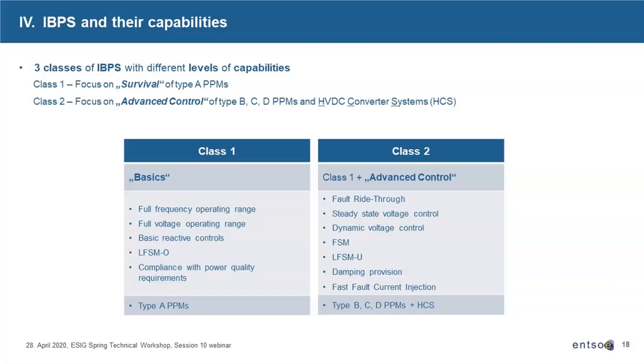So the distinction was made between class one generators, which shall cover some basic functions, which means that they shall be able to operate stably and autonomously over the typical operating ranges of frequency and voltage, and provide the basic controls, the basic frequency related behavior by the LFSM-O, limited frequency sensitive mode at over frequency functionality. This is typically what we expect from the smallest generators in the system, at domestic levels, PV installations, to operate stably and to have these basic capabilities.